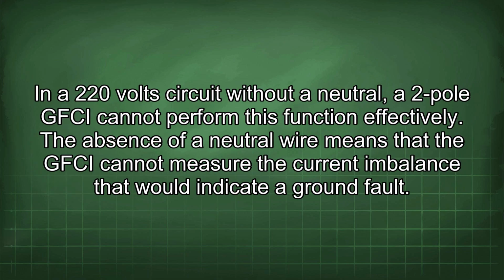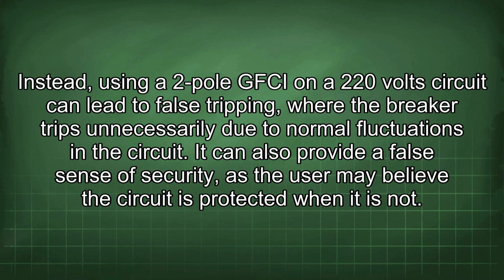In a 220 volt circuit without a neutral, a two-pole GFCI cannot perform this function effectively. The absence of a neutral wire means that the GFCI cannot measure the current imbalance that would indicate a ground fault. Instead, using a two-pole GFCI on a 220-volt circuit can lead to false tripping, where the breaker trips unnecessarily due to normal fluctuations in the circuit.